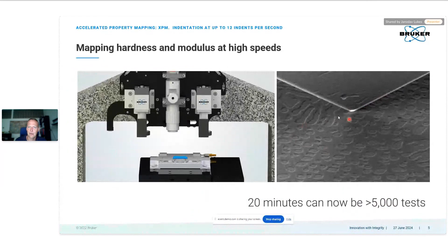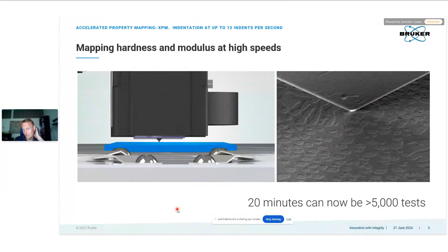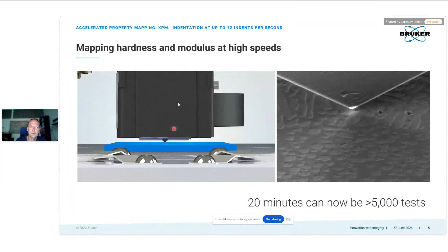So the very latest Triboindenter TI990 from Bruker enables 12 indents per second. So you are running the indents in a line, and you might actually get the contrast in mechanical properties with respect to the different phases. How that works: you are focusing on a surface with a microscope, and then you synchronize the motion of a piezo scanner over the sample surface with the sensor that produces the indents and collects the indentation curves.